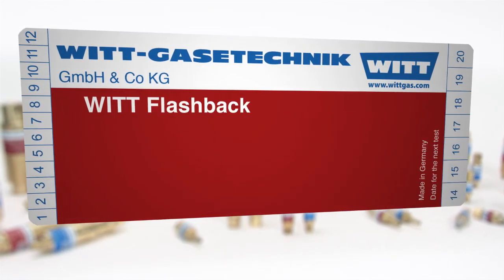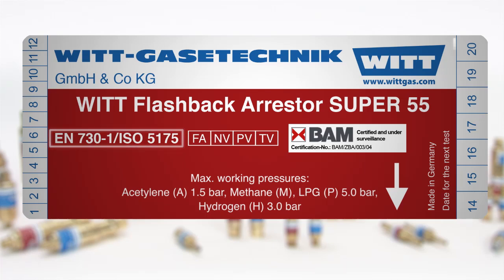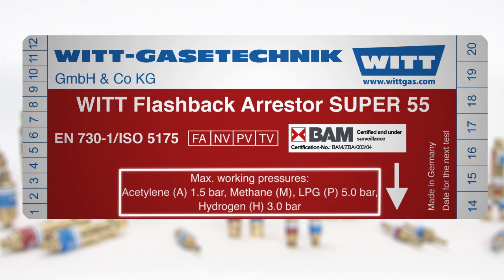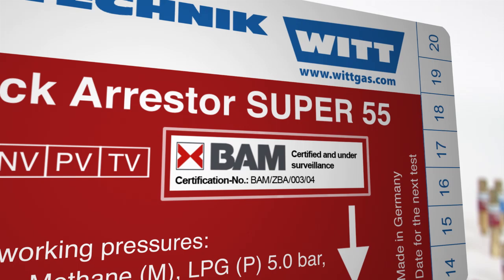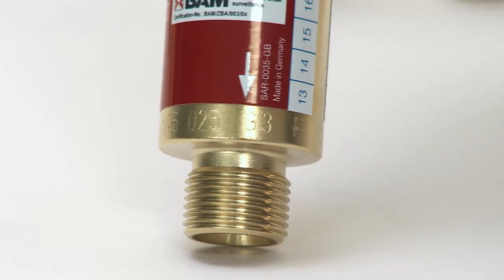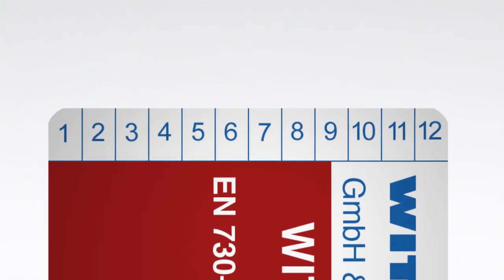Safety begins with the product label. Flashback arrestors according to EN 730 Part 1 must be labelled with the following information: certification number of the standard, manufacturer name, model name or type designation, gas types and maximum operating pressures, flow direction, and safety elements of the device. The certification number of an external test body provides the certainty that compliance with the standard has been inspected by an independent authority. For complete traceability of every individual device, the article number, date of manufacture, and serial number are engraved by WITT. The labels also provide practical marking options to note the date of the next test directly on the device.